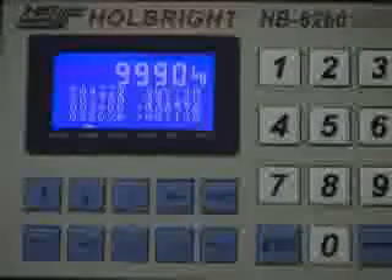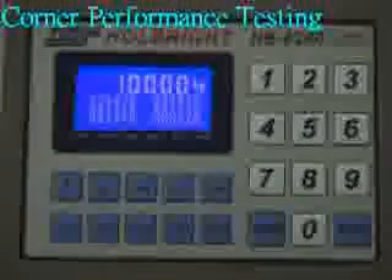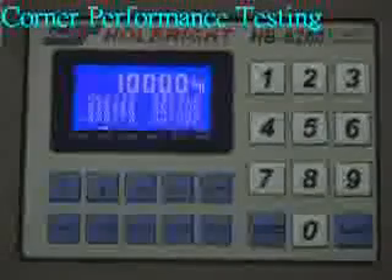Now we are going to check the truck scale's corner performance after calibration. Place the standard test weight of 10,000 kg on the first corner — the weighing value is 9,990 kg. Second corner: 10,000 kg. Third corner: 10,000 kg. Fourth corner: 10,000 kg.